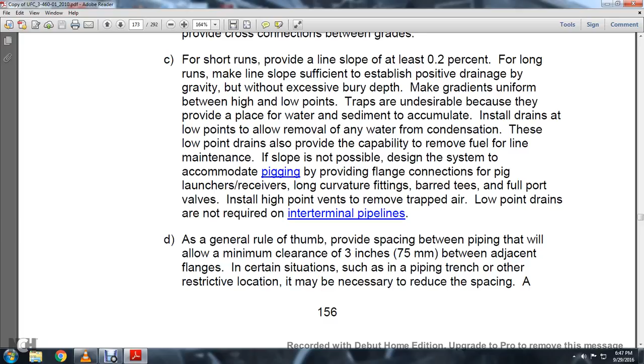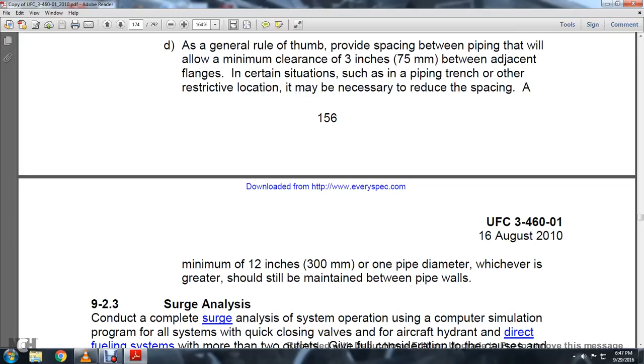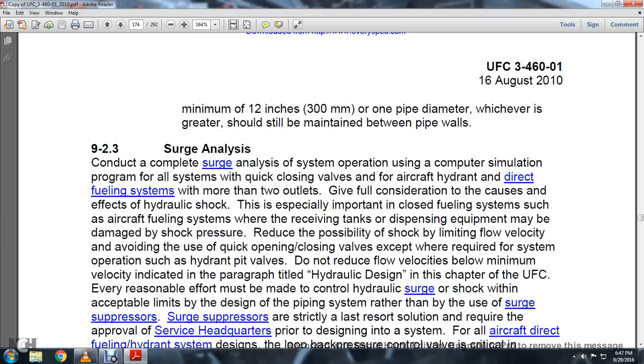As a general rule of thumb, provide spacing between piping with a minimum clearance of 3 inches between the adjacent flanges. In certain situations, such as a piping trench or other restrictive location, it may be necessary to reduce the spacing. A minimum of 12 inches or one pipe diameter, whichever is greater, should still be maintained between the pipe walls. 9.2.3 Surge analysis.